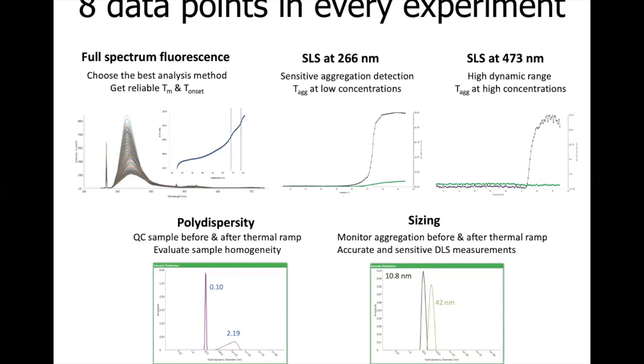A single Tm/Tagg experiment provides eight data points. Full-spectrum fluorescence for every temperature point allows for flexible data analysis and determination of both the TM and onset of unfolding. SLS data from two different lasers — 266 nm and 473 nm — provides aggregation onset temperatures. SLS 266 has greater sensitivity and allows for detection of aggregates at lower concentrations, while SLS 473 extends the dynamic range and can measure aggregation at higher sample concentrations. The DLS measurements provide size and size distribution data at initial and end temperatures, as well as polydispersity.